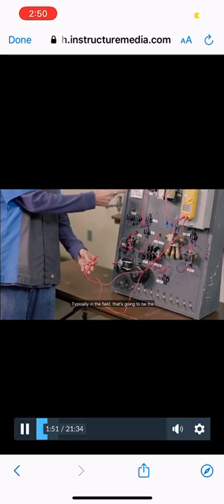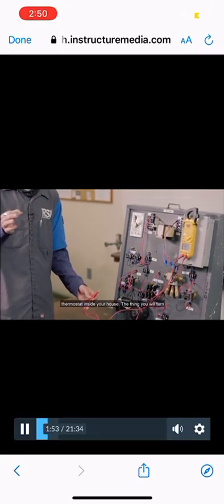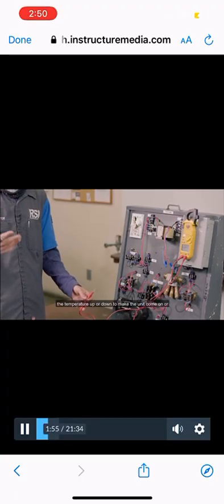So I'm going to look at who tells these two relays what to do. Typically in the field, that's going to be the thermostat inside your house, the thing you turn the temperature up or down to make the unit come on or off. So I want to start there, but I'm already either up on the roof or in an attic, so I'm not going to waste my time climbing back down. So I'm going to go to where the power comes into the unit and starts here.